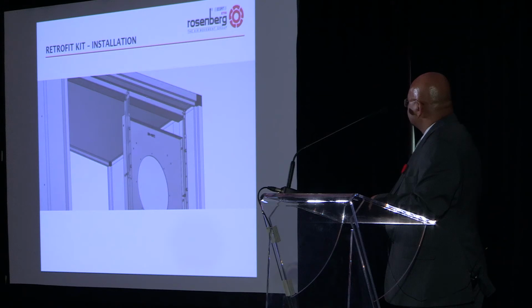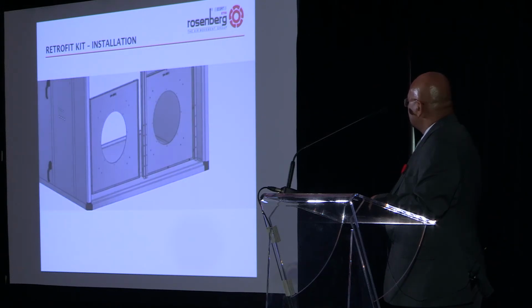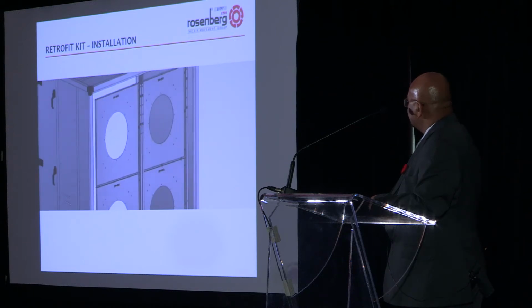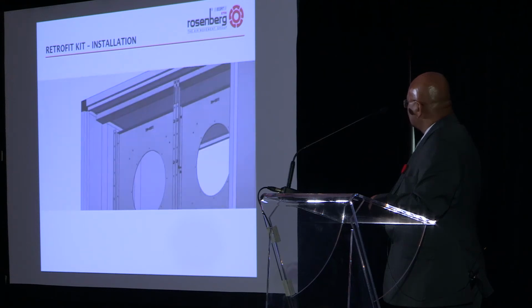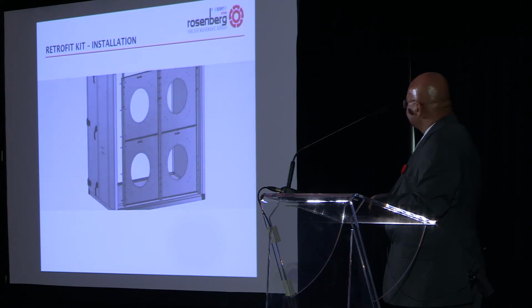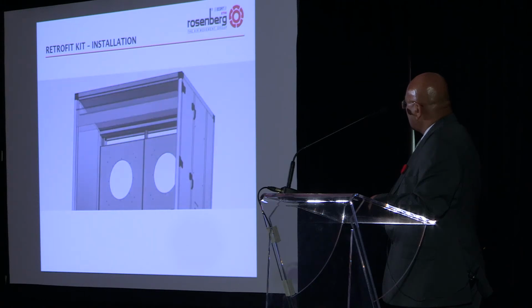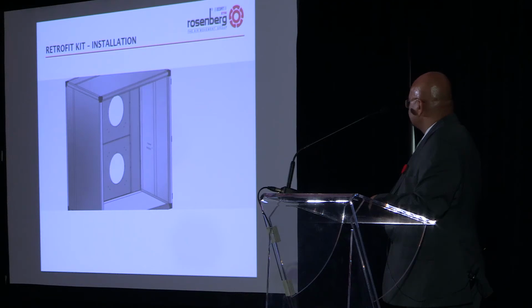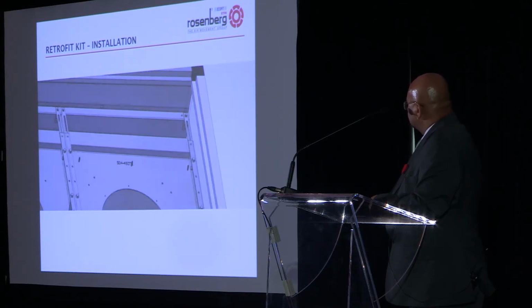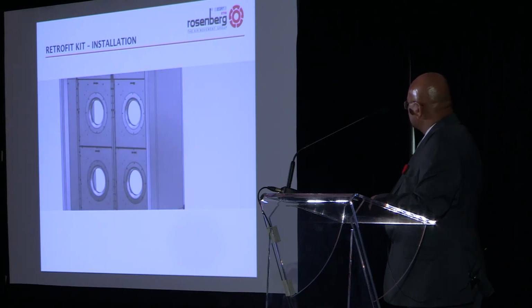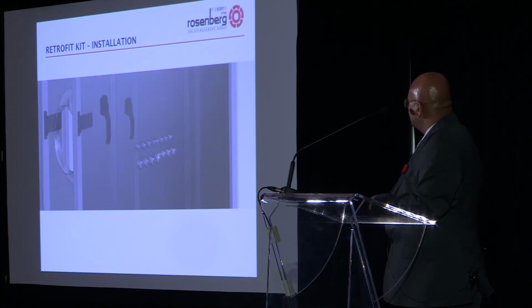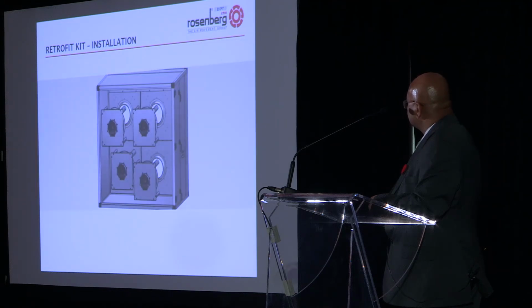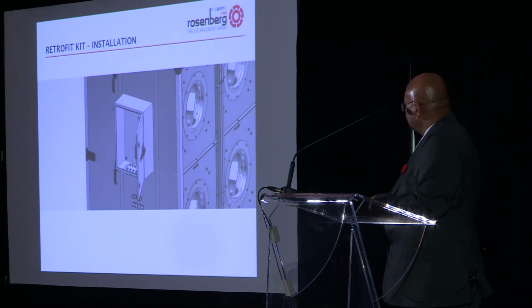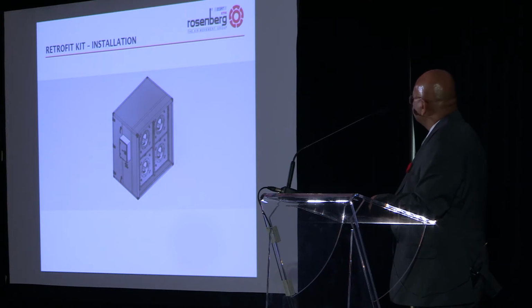Second one coming in. Now you have the second set of the cone plates, which gets fitted with the hardware. Then you have the last rail, which gets fitted to the casing again. And then from the back, you can see the fillers, which go on the top and on the side. So all these are the hardware. Now is the cone plate, which goes inside the actual cone. Then you're hooking up the tubing. The fans come in, all 4 fans together. This is the wiring cabinet, which gets hooked up to the system. So this is how we install the retrofit fan grid inside any AHU. Very simple.